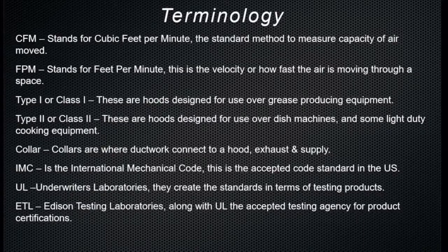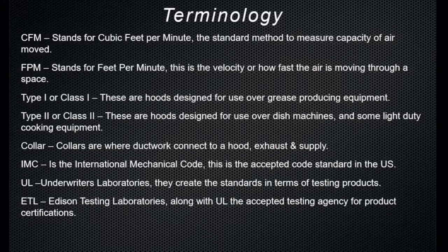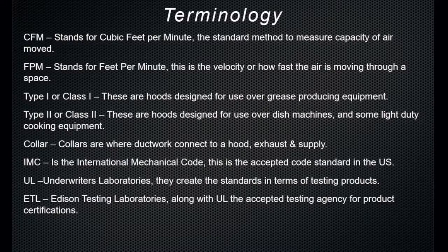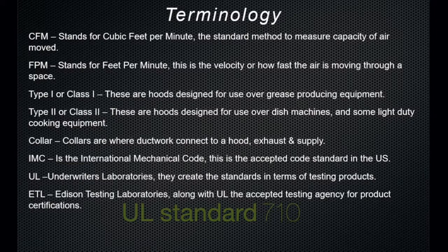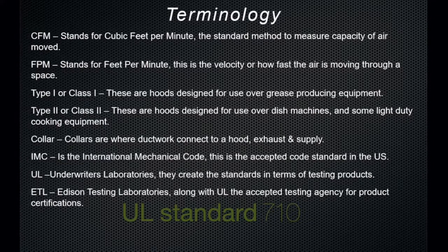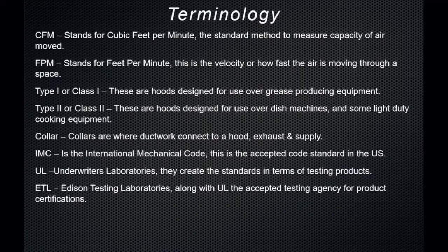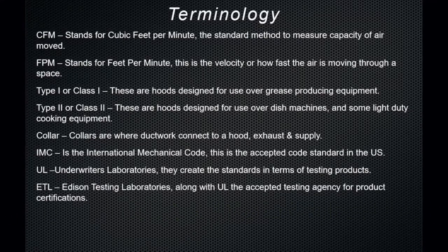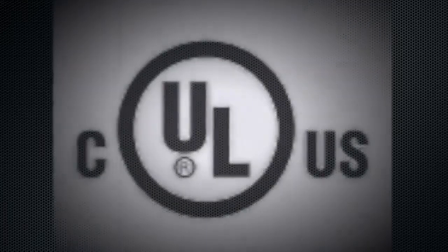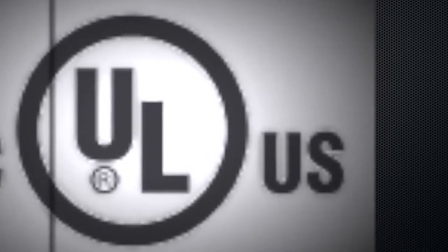You use the same kind of process with hoods, whether that's part of the construction method of a hood or for capacities. They have UL standard 710 is the category that hoods fall under, and everybody is tested to that same standard. ETL is Edison Testing Laboratories, and they're a company a lot like UL, but instead of making the standards, they do testing only. So if you can have a ETL listed component or a UL listed component, they should be exactly the same kind of quality. They're tested at the same standards. It's just a different company that actually does that test.